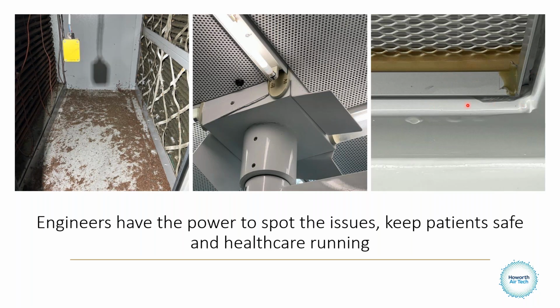And this is what gel does, it changes state. Here it's quite viscous almost, and it holds into the channel. Because of its application and the way it was put together, it turns to a liquid and moves around and can start to almost drop off. If you do have operating theatres with these in - and UCV systems have never had gel seal filters in - we can come in and replace that and put a PU gasket in, so no dripping would happen.